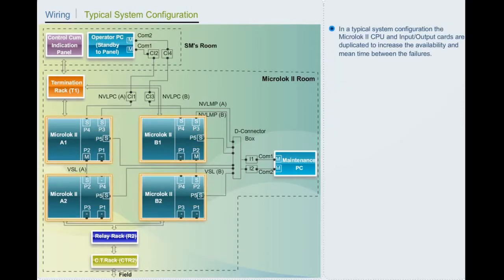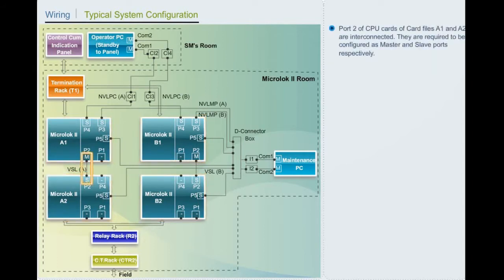In a typical system configuration, the Microlok II CPU and input-output cards are duplicated to increase the availability and mean time between the failures. The card files A1 and A2 of Microlok II are duplicated as B1 and B2. Port 2 of CPU cards of card files A1 and A2 are interconnected. They are required to be configured as master and slave ports respectively.